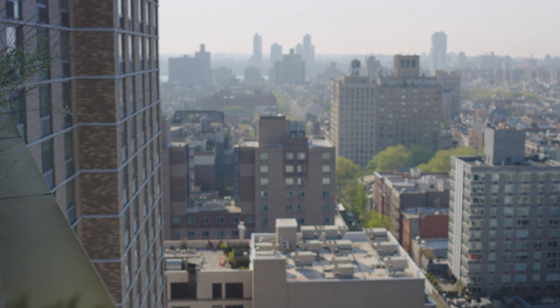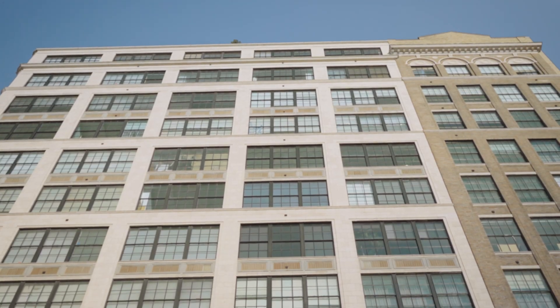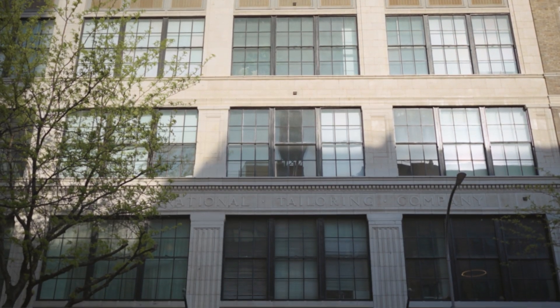Right now we have an envelope that isn't the best, and quite often I've seen buildings think: 'Our envelope isn't great, so why would we invest in these other systems?' But what we've realized is that we can put this in play today, and as the building makes incremental improvements on its assets when they reach end of life, we're actually compounding the value of this project. For example, when we improve the windows, we can start lowering the temperatures of the building system, which makes our water source heat pump system even more efficient.